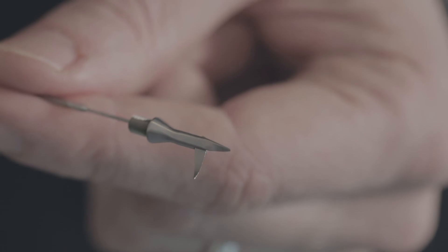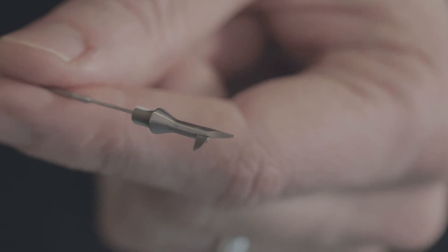Matthias is back from the repair hub — let's see what he did. I sharpened this micro scissors with this file. Like I said before, this is just for the last step. With this kind of file you get it sharpened like brand new. It looks really good — the edge just looks polished. That's quite good quality. So to sum it up, the quality of the file is really good, and they last much longer than the regular files. I don't know exactly how many times longer, but way, much longer than regular ones. So what we said in the beginning is true: good quality needs good tools.